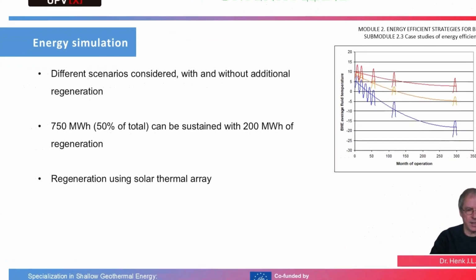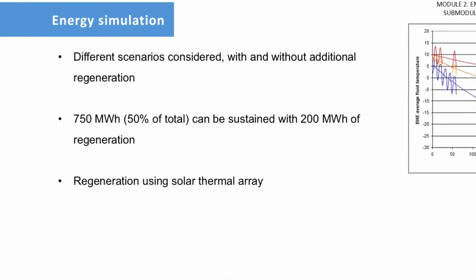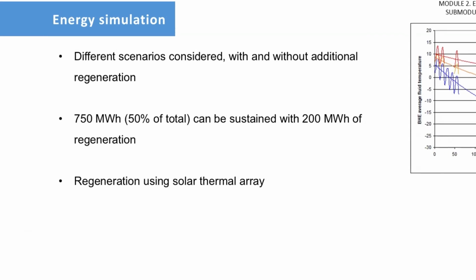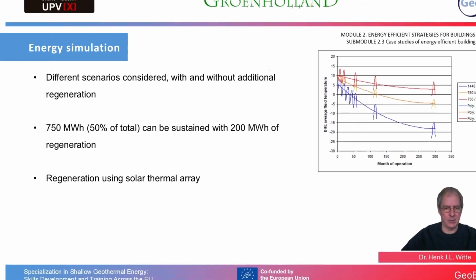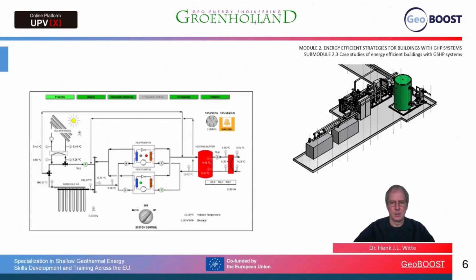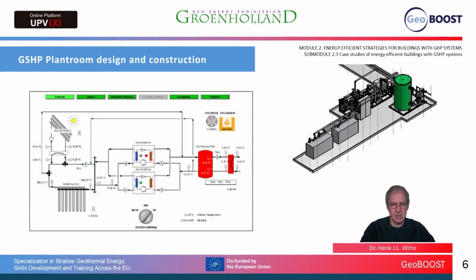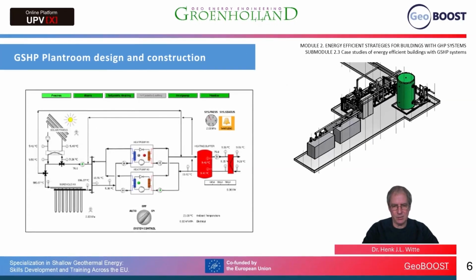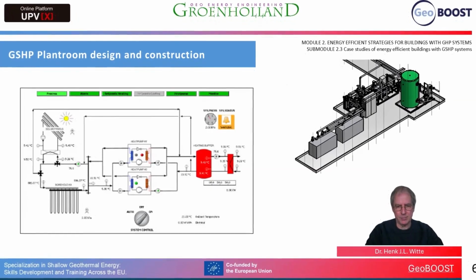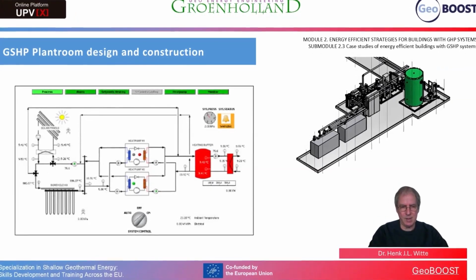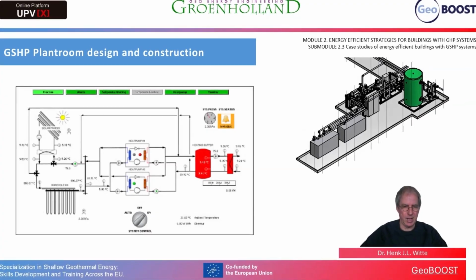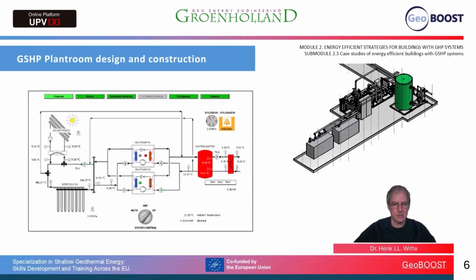Finally, a scenario was selected where we could deliver around 750 megawatt hours of heating, so about half of the total heat demand, with 200 megawatt hours of regeneration included, regeneration due to solar panels. The plant was constructed and delivered to site. You can see in the schematic that we have a heating-only system with a heating buffer connected to the building with a plate heat exchanger and a solar panel array used for regeneration.